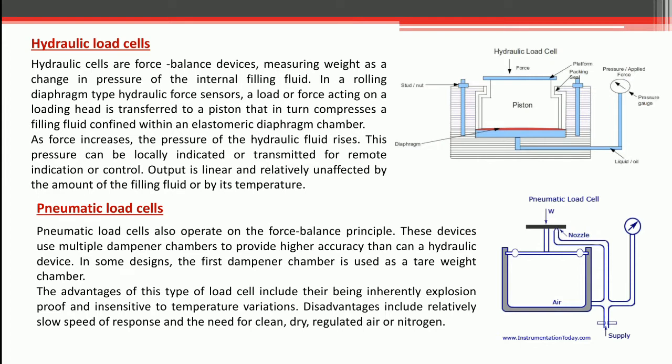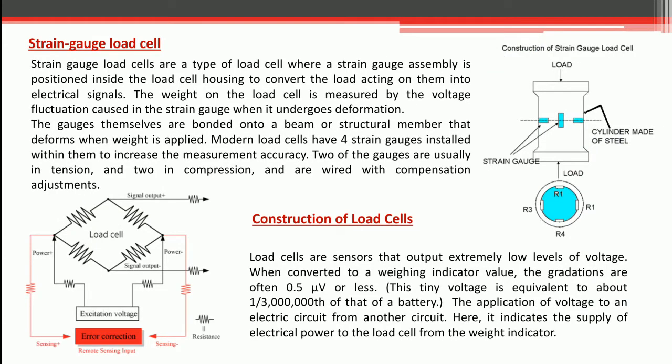The last one we are going to discuss is the strain gauge load cell. Now the strain gauge load cell converts weight or force into electrical outputs which are provided by the strain gauge, and this output can be connected to various measuring instruments for indicating, recording and controlling the force. Usually the strain gauges are directly applied to the force developing device, and the device is then calibrated against the strain gauge output. These are excellent force measuring devices, particularly for transient and non-steady forces, and they are used in conjunction with a CRO for measurement of rapidly changing loads.